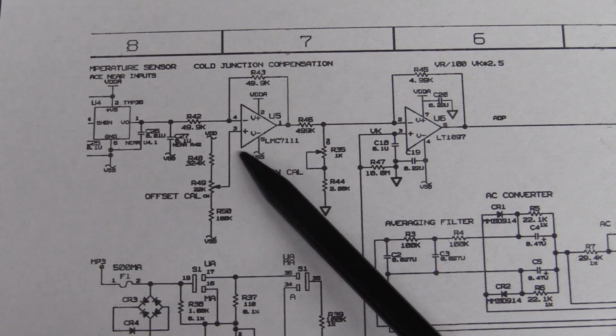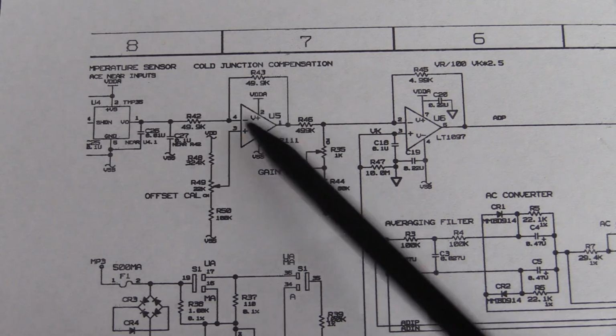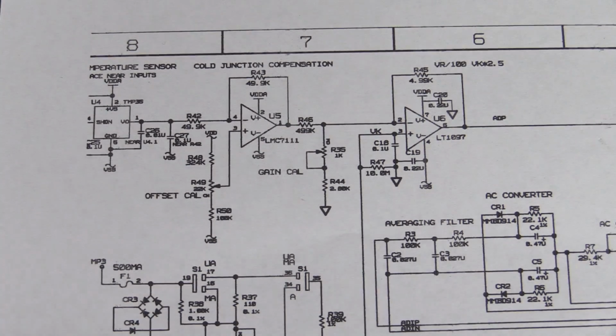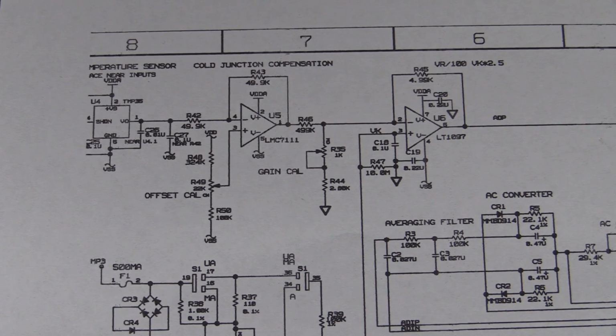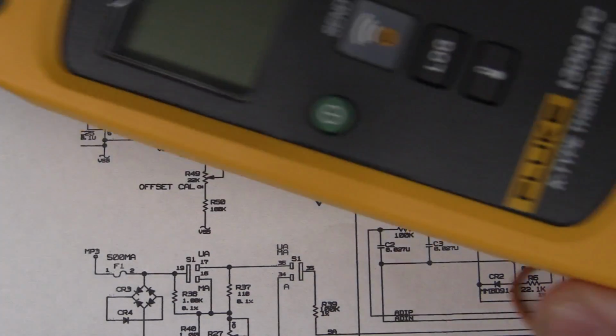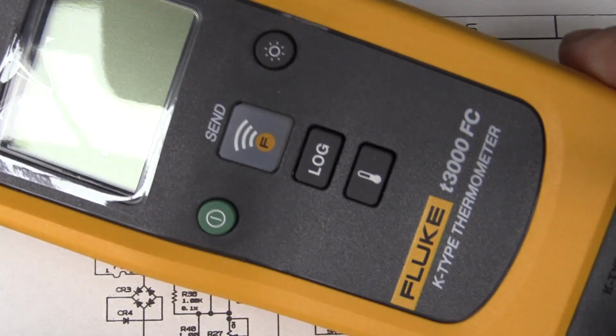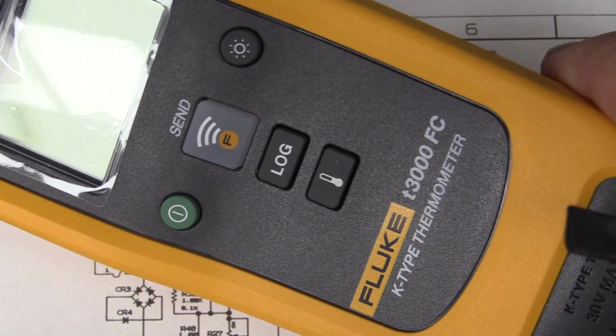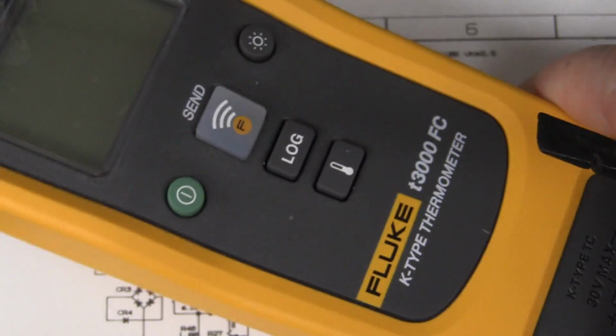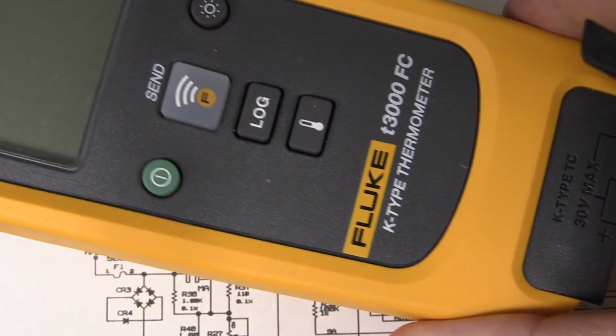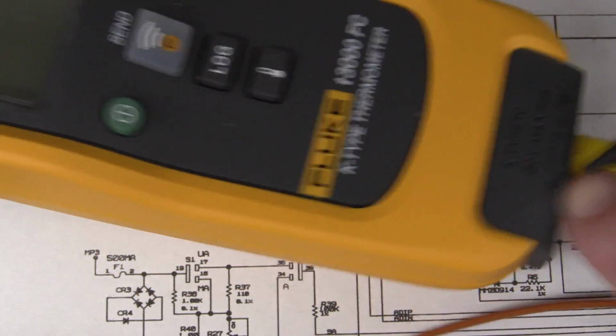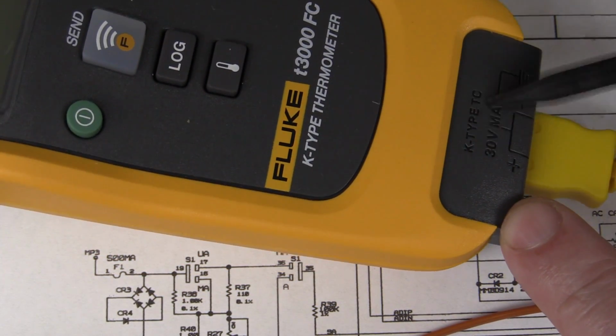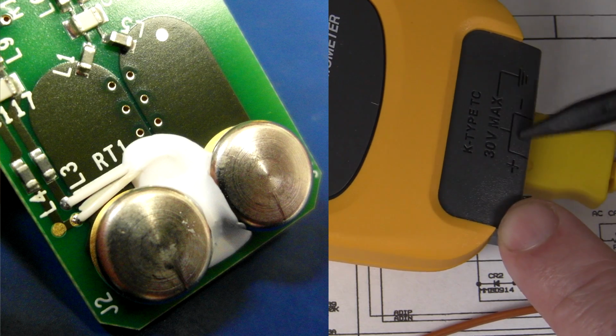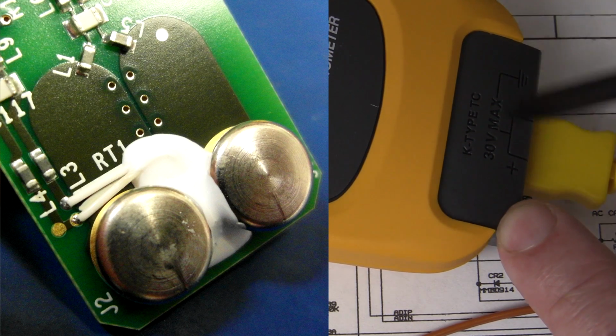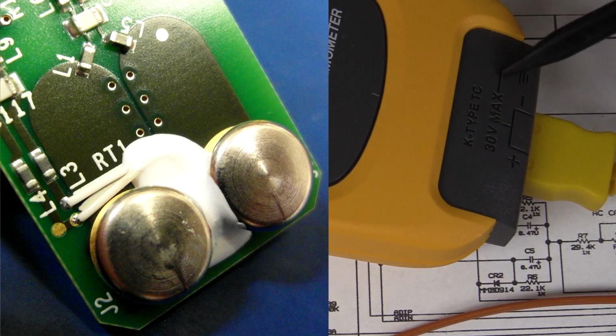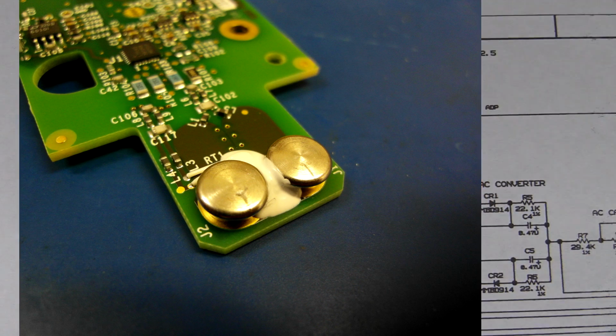And that's what high-end thermocouple amplifiers and thermometers like - hang on, I've got one here somewhere - like this Fluke K-type, the Fluke t3000 FC. I've done a teardown of this and various others, and these have cold junction compensation on the input pins here. They have a temperature sensor which takes into account the temperature of the dissimilar metals, which can cause offset errors in your temperature.